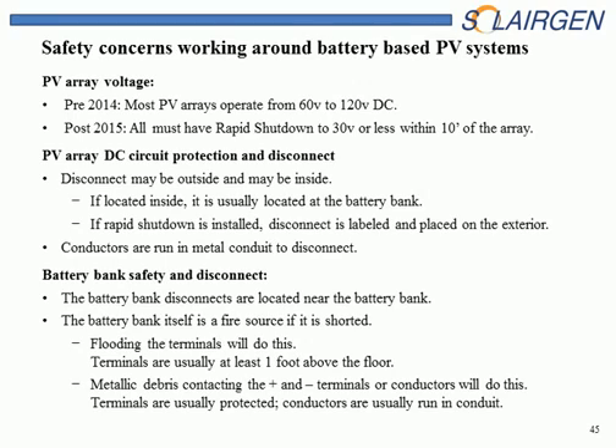PV array disconnect protection. It may be outside, it may be inside. If it's a ground mounted system, it's probably outside. If it's a roof mounted system, then you hope that it's outside. That makes your job a lot easier if you can trace that conduit. If it's located inside, then you're going to have to look either at the basement or in the garage where it's probably located.